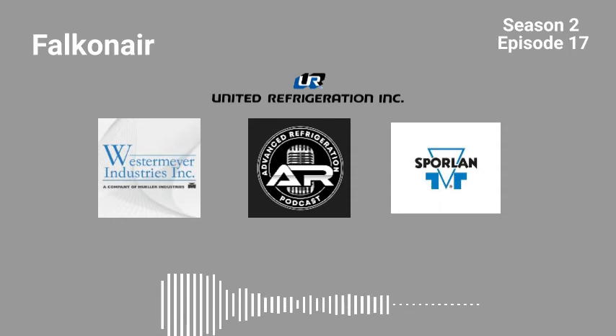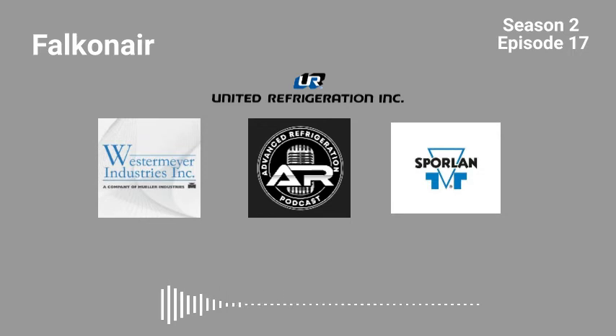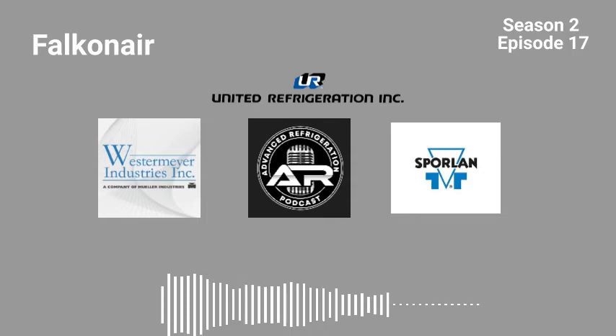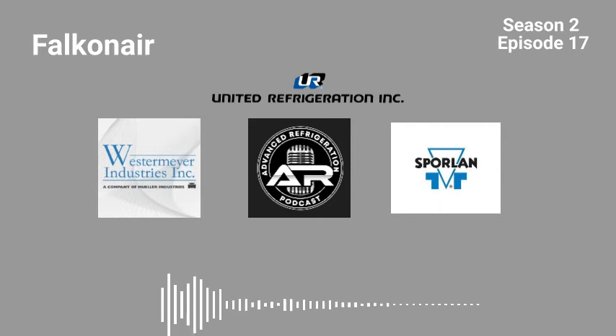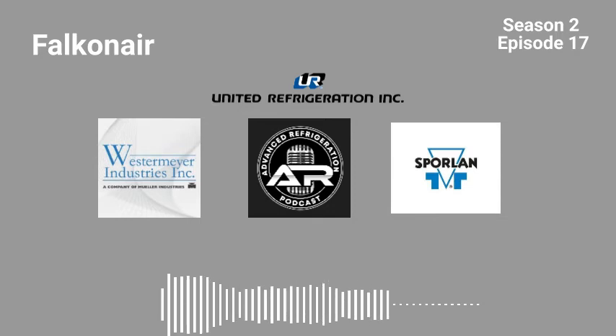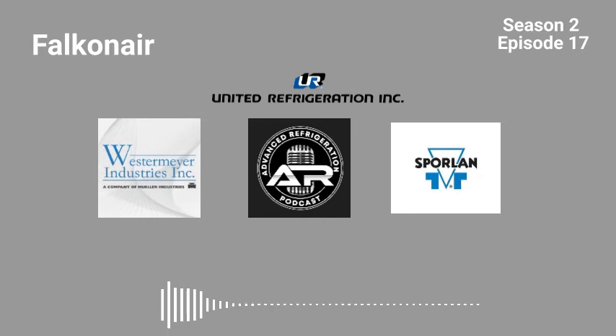But even better, we are now gathering that data, including your amperage and your voltage, and now we can send it to the cloud. So now you can see your settings, your VFD, your consumption, live or recorded on the cloud. Tell them a little bit more about that, Chris. We are still in testing mode at the moment, because we do a lot of testing before we outlay something. But we have a plug-in board that plugs into the SCC that we're talking about. You can connect it to the internet, and then you can see the 2 temperature sensors, the frequency on your drive, the voltage, the amps, and the kilowatt consumption live on the cloud. You can either have it recorded, so you can go back through history data, or see it live. And you can only do that by Modbus.